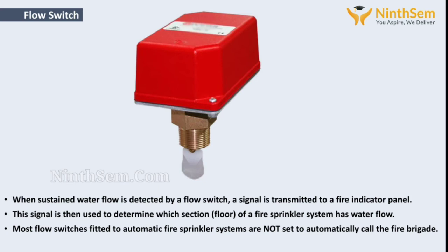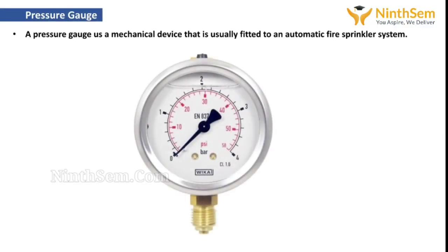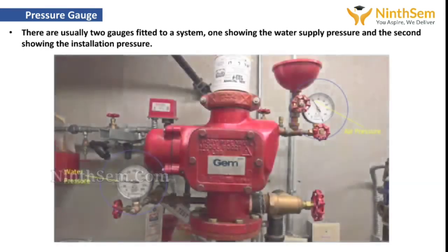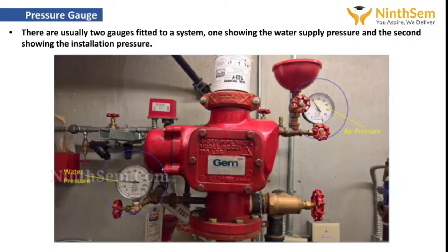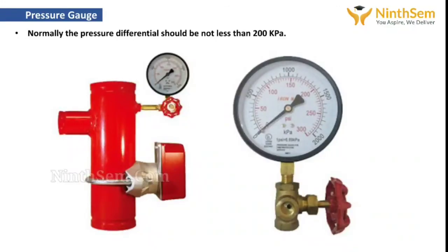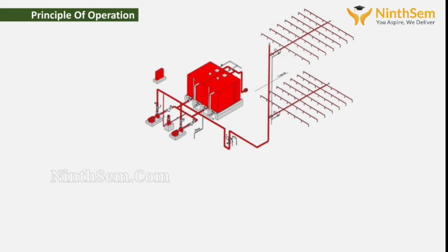So next, the pressure gauge. A pressure gauge is a mechanical device that is usually fitted to an automatic fire sprinkler system. There are usually two gauges fitted to a system, one showing the water supply pressure and the second showing the installation pressure. Normally the pressure difference should be not less than 200 kilopascal. Let's discuss something important, which is the principle of operation. The principle of operation of a fire sprinkler system, an automatic fire sprinkler system.